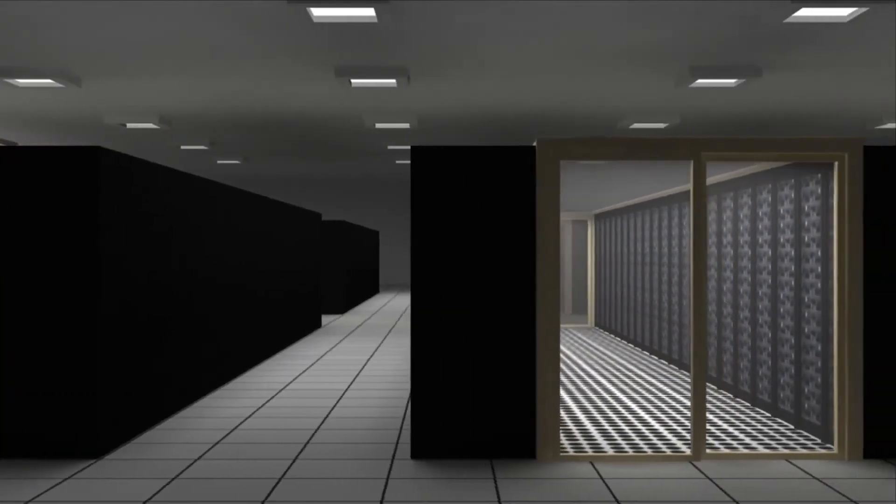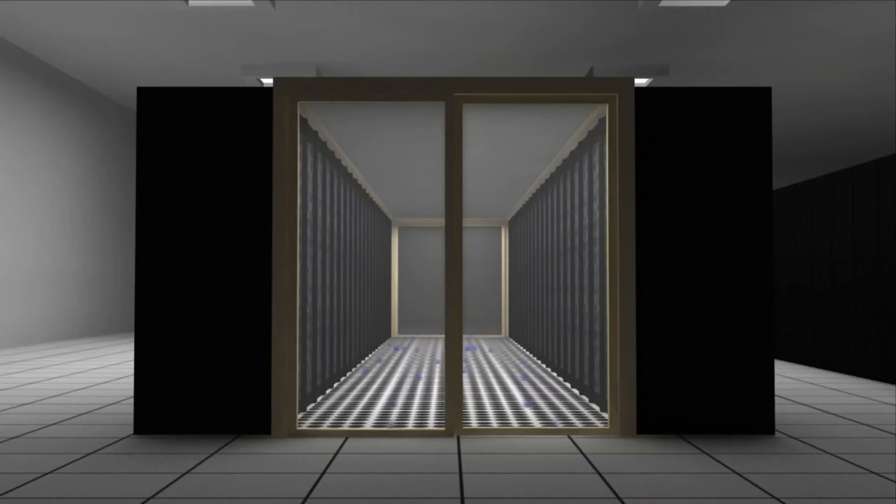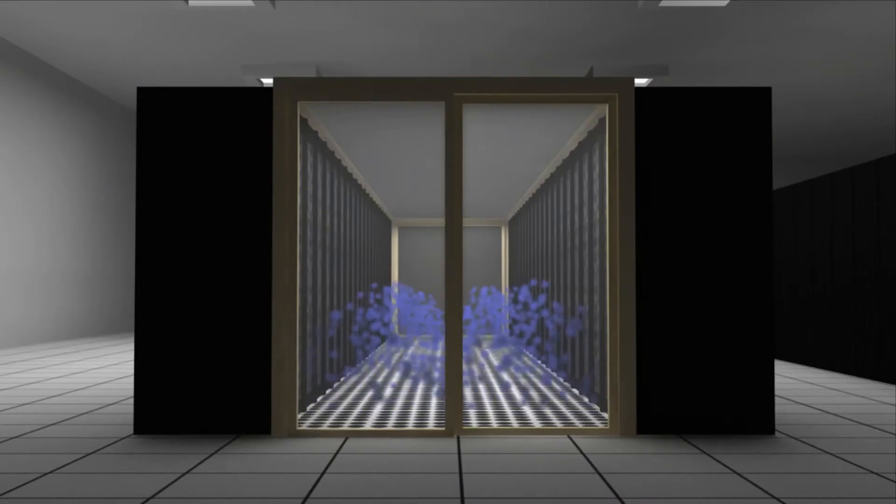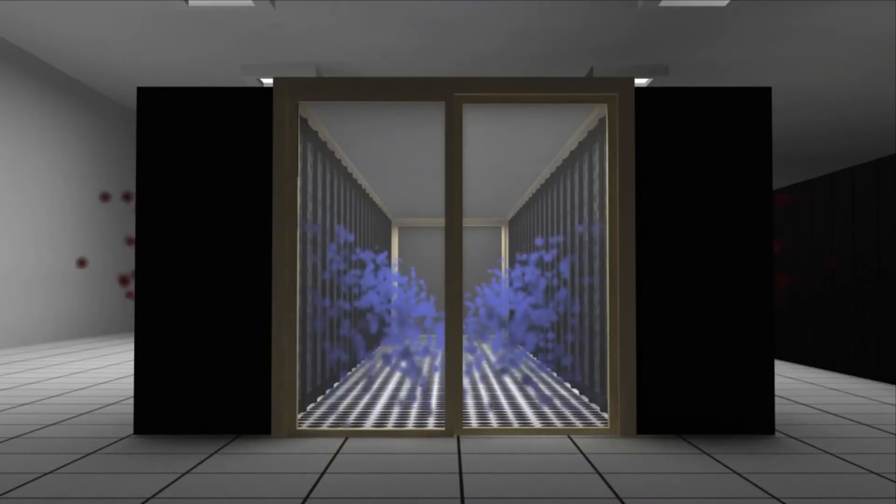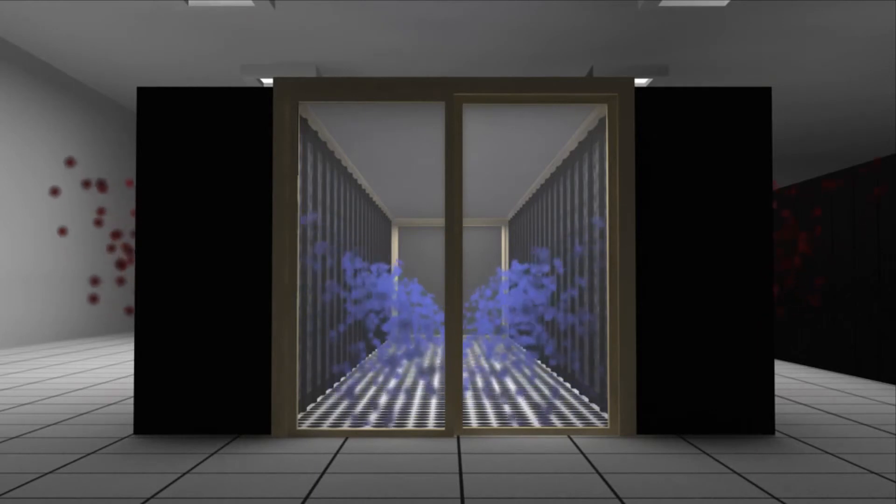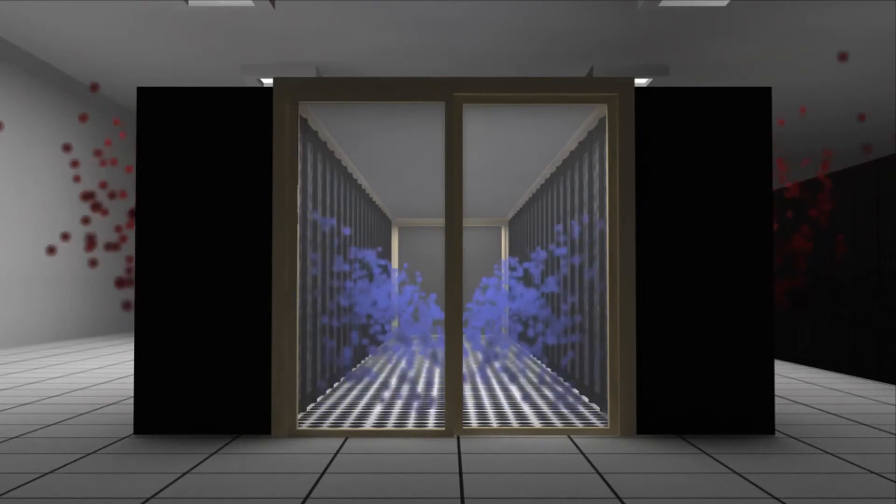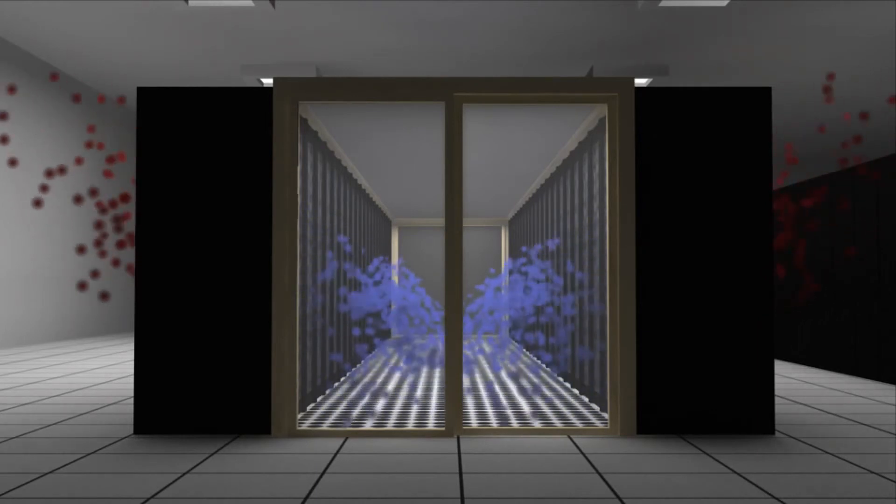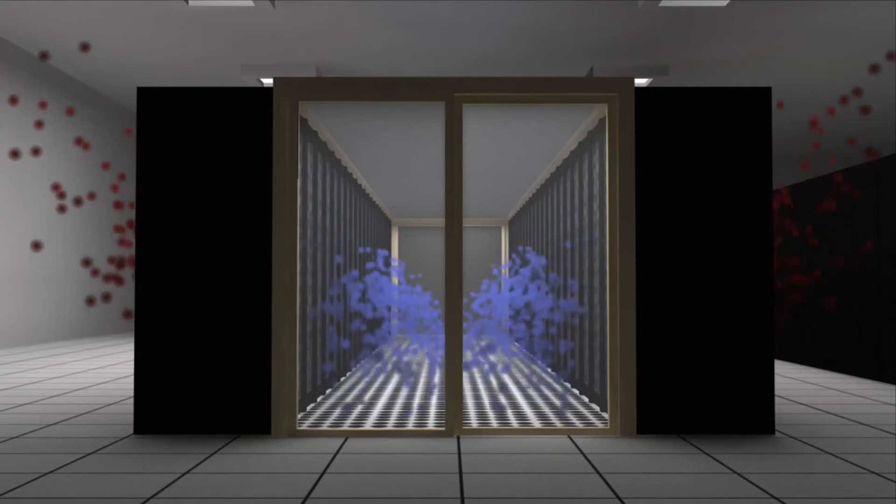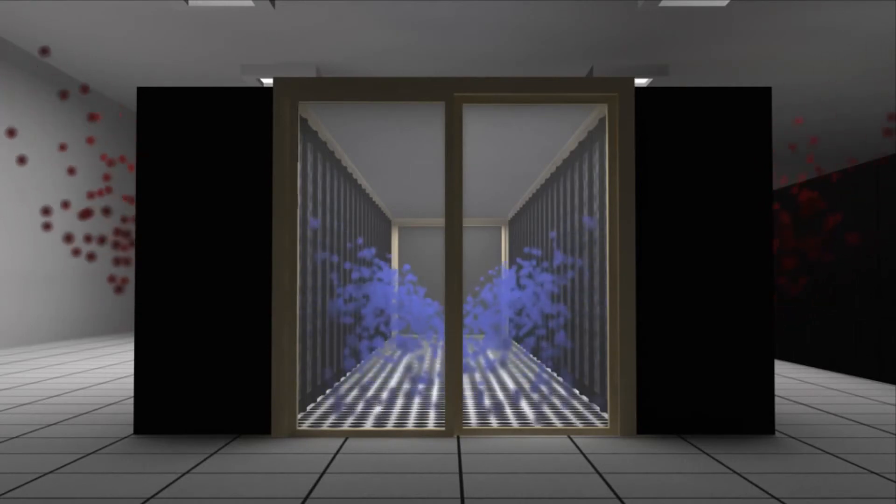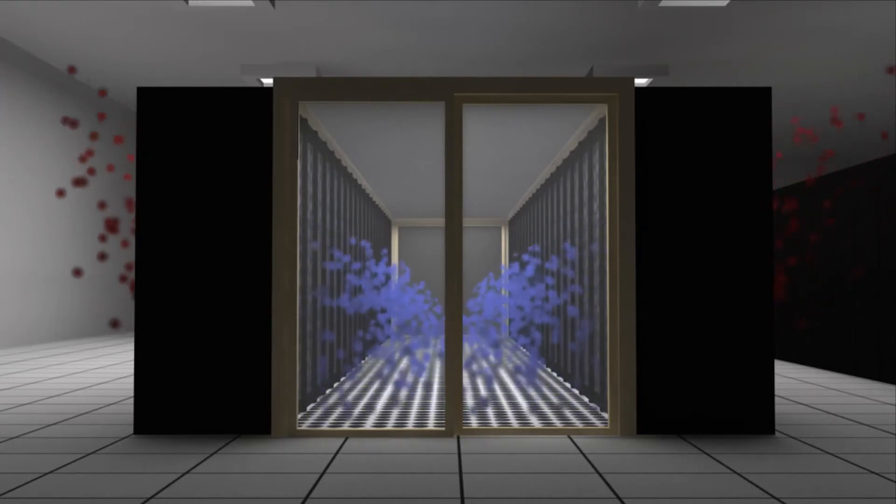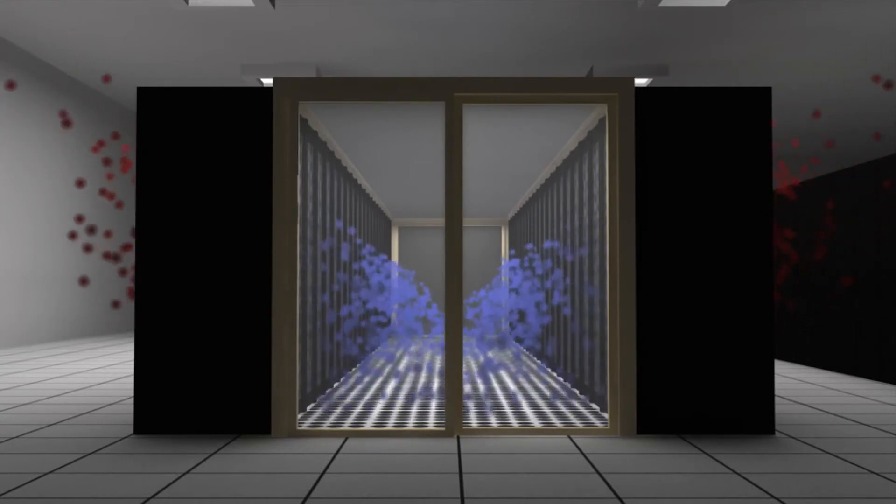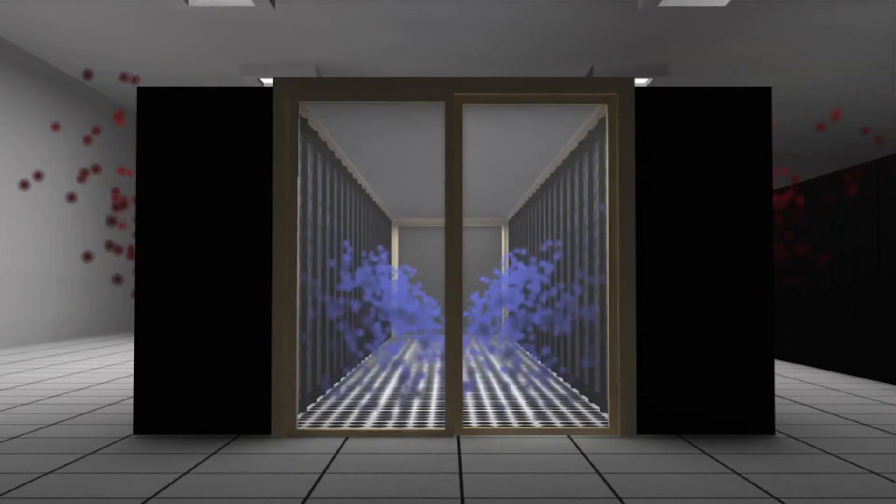In order to improve the efficiency of the cooling system, the area of the cold aisle is contained so that the cold air does not mix with the hot air in the rest of the room, and the entire data center acts as a hot air plenum. Although the temperature of the room rises, the air reaching the servers is cool, thus bringing in more efficiency.